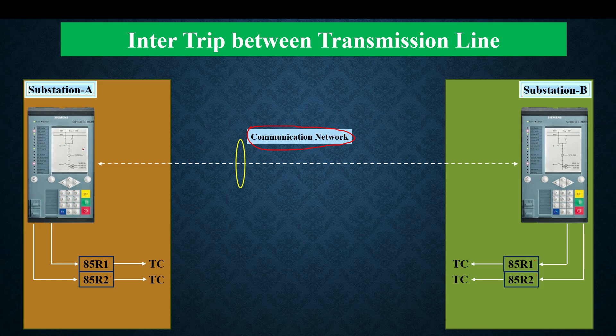If a delayed protection operates — for example distance protection zone 2, zone 3, or zone 4 — it is a delayed tripping case. The delayed trip inter trip signal will go to substation B and operate 85R2. Both 85R1 and 85R2 will trip the circuit breaker, but the difference is 85R1 is a self-reset relay that initiates the auto-recloser, whereas 85R2 is a lockout relay that blocks the auto-recloser.